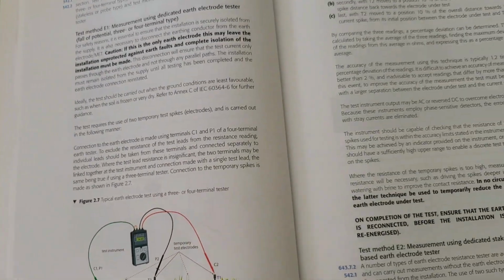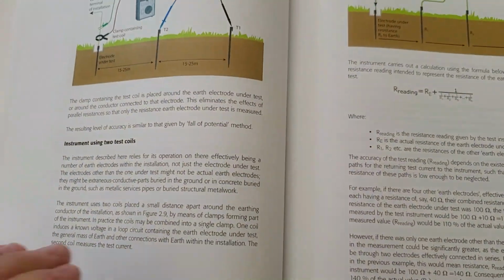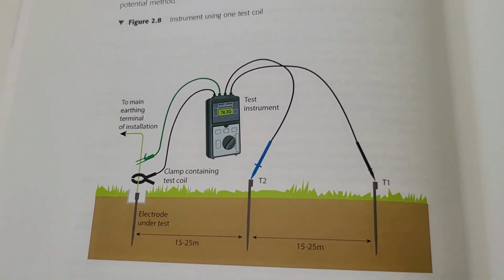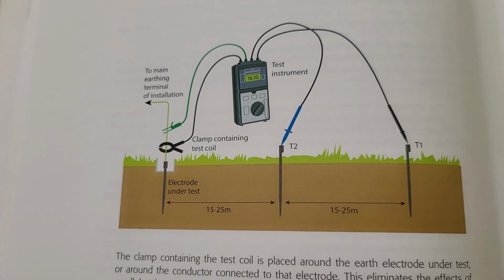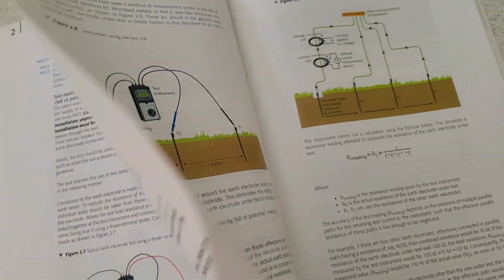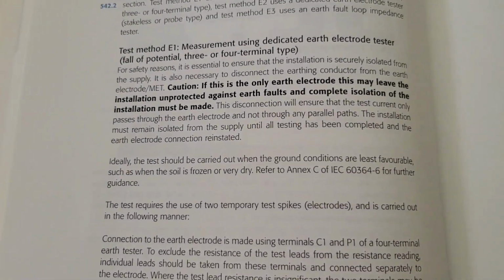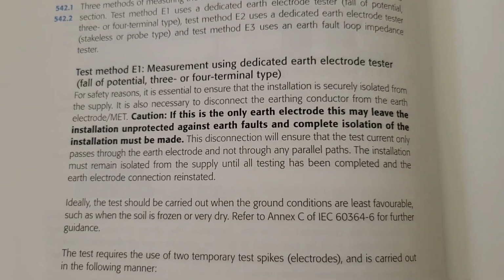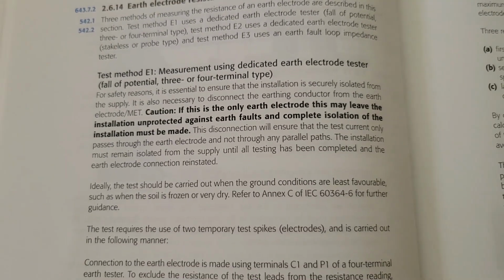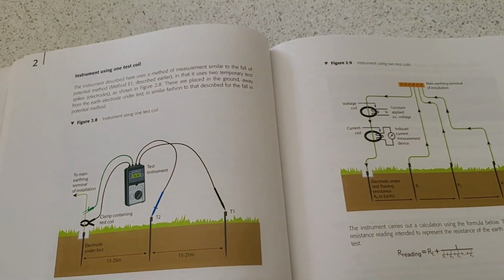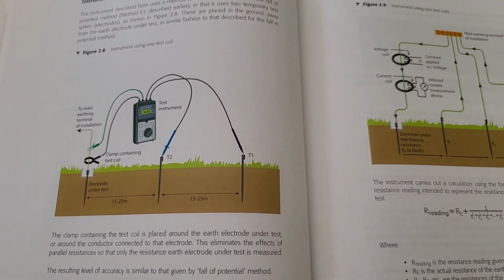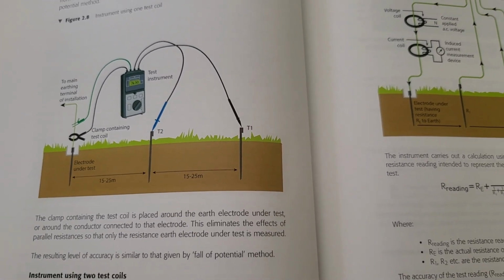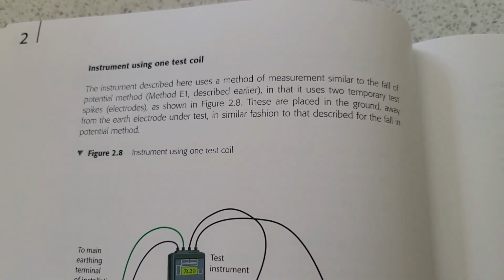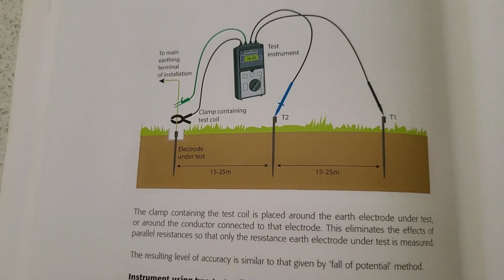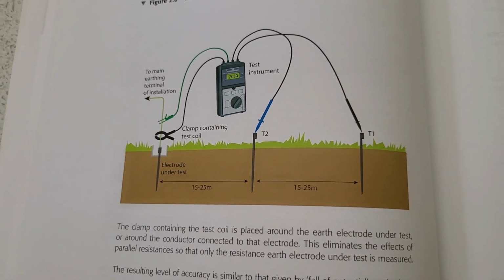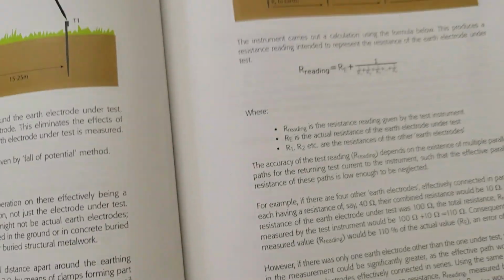We've covered it in the video, but it's there in the book if anyone wants to go off and read it. You've also got the coil where you can use a clamp meter. So if you can't disconnect the earthing system, and that's another point to note actually that they reference here, that if you are working on the electrode and need to disconnect it, make sure it's not providing a means of earth for any other part of the install. So I was lucky down at the shed, there's nothing else that uses that, so I can crack on without having to turn the entire install off. But if that's not the case for you, make sure you are considering that. But yeah, you can put the clamp around the earth and use your spikes out into the mass of earth and get your test measurements as well.